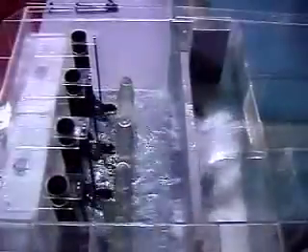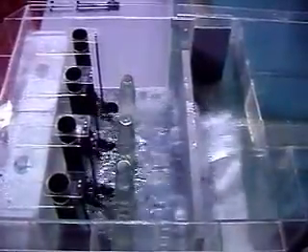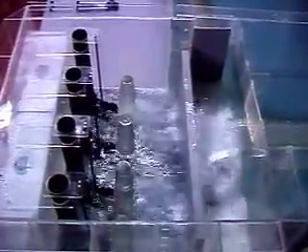Some of the solids float on the surface. Improper sump design and pump control can cause buildup of a mat on the surface. When the mat breaks up, large pieces might enter the pump inlet, causing disturbances in the pump operation. Those problems can be avoided with correctly selected pump control and good sump design.